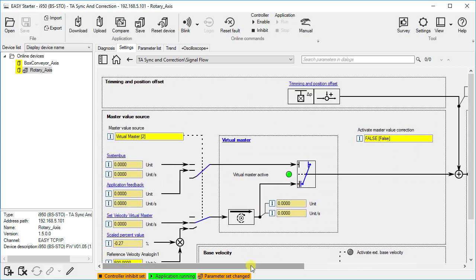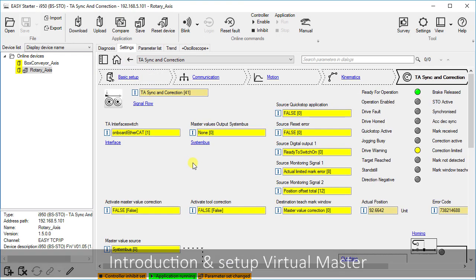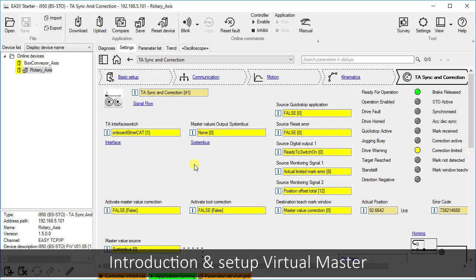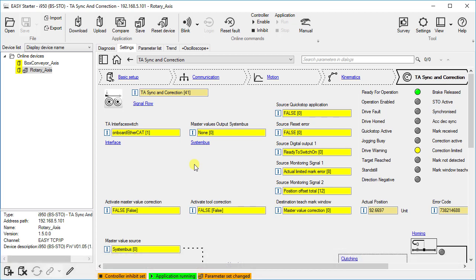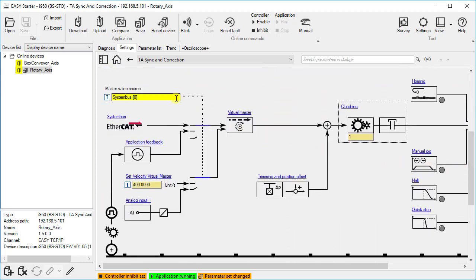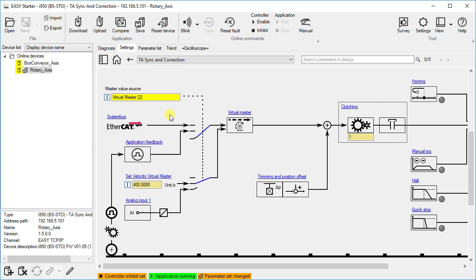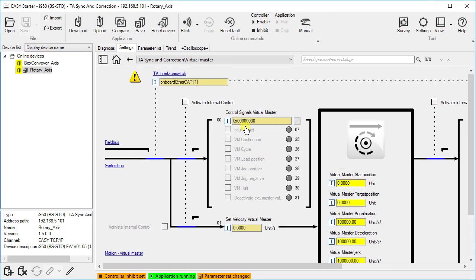Go back to the TA overview. A device in a synchronized network of drives takes on the role of the master while serving as the first slave drive. It generates the master value and transmits it to the slave drives. In our case we will run the rotary axis by syncing it with the virtual master. The signal flow starts with master value source. Here we select the virtual master as source. Additionally, we need to configure the virtual master so that the rotary axis will just follow it. Click on to virtual master. A new interface opens where you can configure the behavior and activate several operating modes and functions of the virtual master via the control signals.